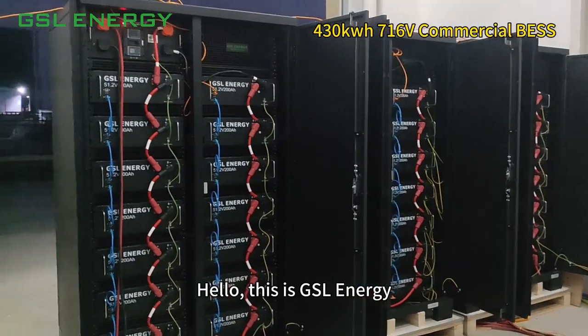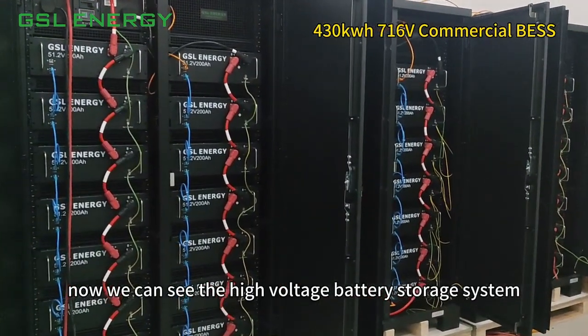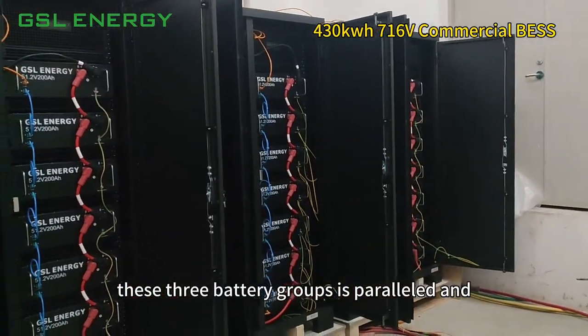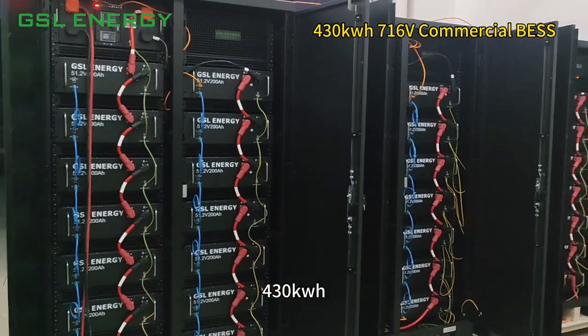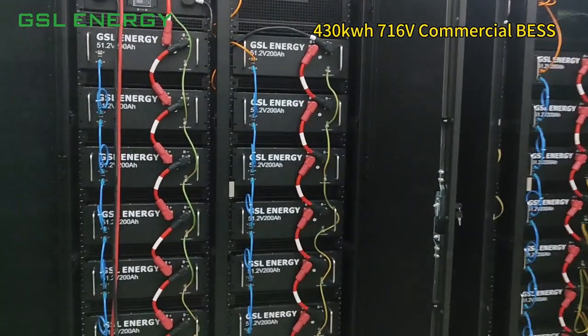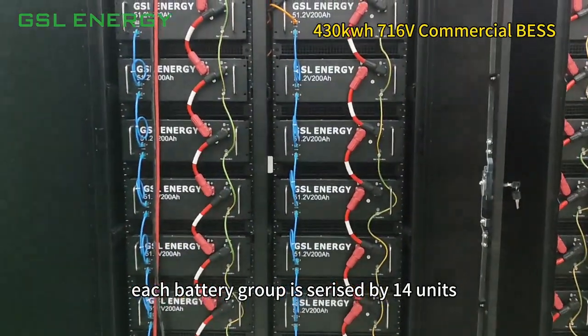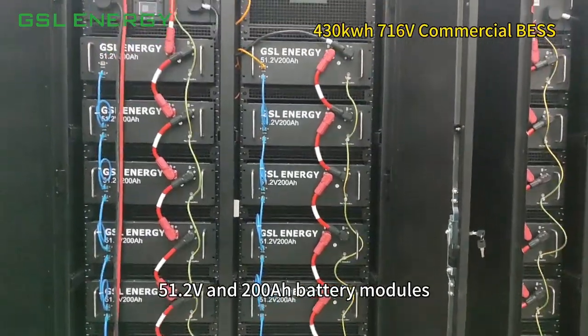This is GSL Energy. We can see the high voltage battery storage system. These three battery groups are paralleled and can reach up to 430 kWh. The voltage can reach up to 720 volts. Each battery group is comprised of 14 units in series — 51.2V and 200Ah battery modules.